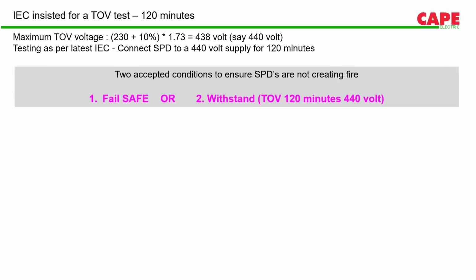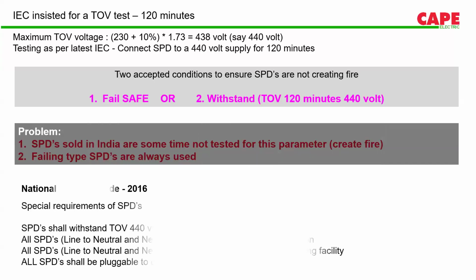Because of this problem, the IEC standard introduced a test called the TOV test. Every SPD has to be tested with a temporary overvoltage for 120 minutes. For 2 hours, the SPD is given 440 volts across its terminals. The standard says there are two acceptable results. One is that the SPD withstands 440 volts for 120 minutes without any change in parameters. That is acceptable, of course. The second acceptable result is that SPDs are allowed to fail, but they are not allowed to create fire or blast. So the second acceptable condition is the fail-safe condition.